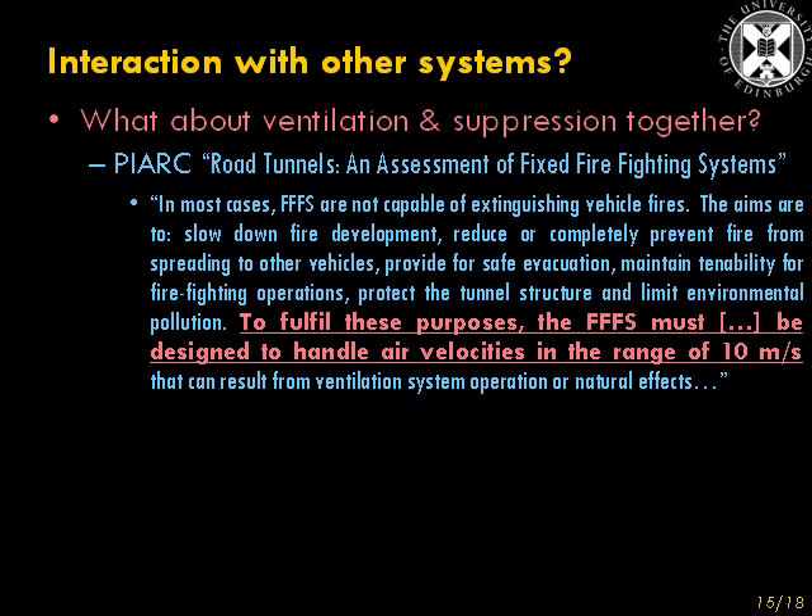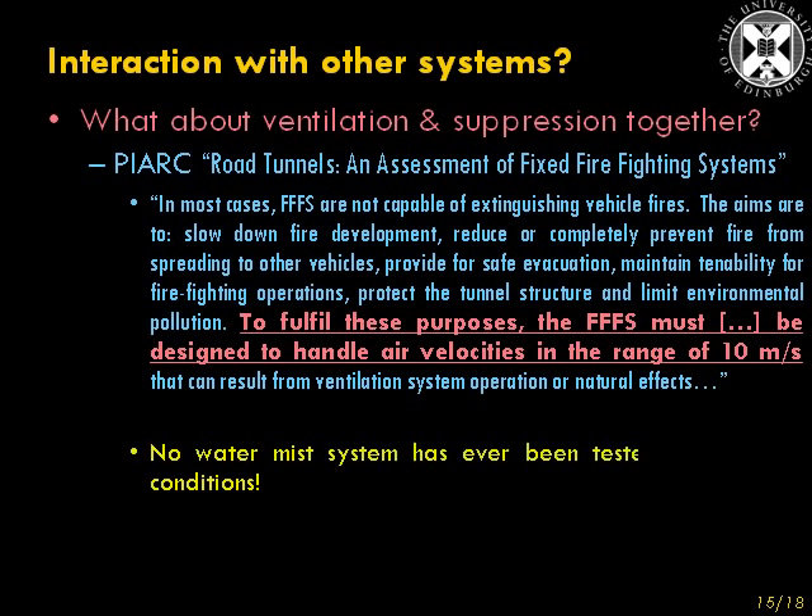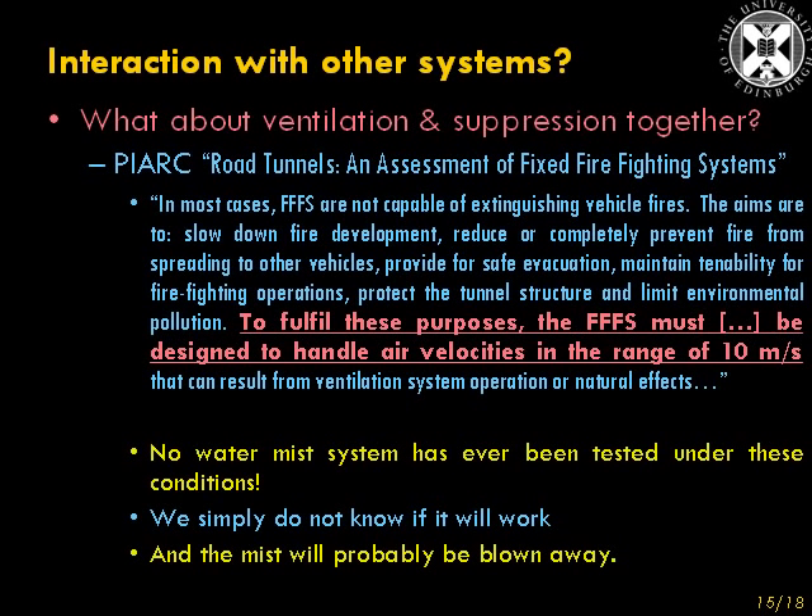So what about using ventilation and suppression together? A recent publication by the World Road Association, PIARC — their 2008 publication called Road Tunnels: An Assessment of Fixed Firefighting Systems — states: 'In most cases, fixed firefighting systems are not capable of extinguishing vehicle fires. The aims are to slow down fire development, reduce or completely prevent fire from spreading to other vehicles, provide for safe evacuation, maintain tenability for firefighting operations, protect the tunnel structure, and limit environmental pollution.' To fulfil these purposes, the fixed firefighting system must, amongst other things, be designed to handle air velocities in the range of ten metres per second that can result from ventilation system operation or natural effects. No water mist system — and I suspect no deluge system — has ever been tested under these conditions.